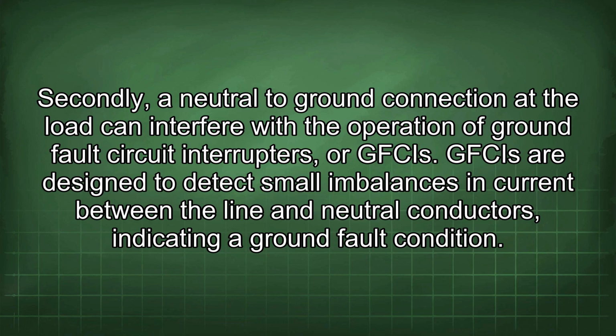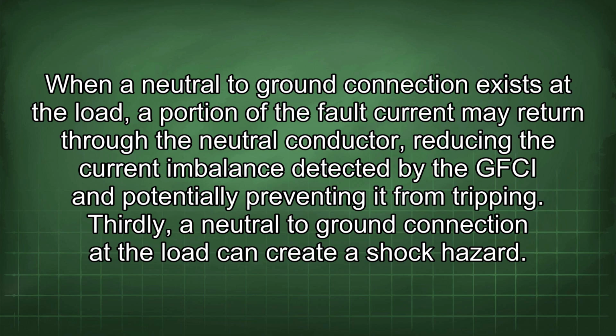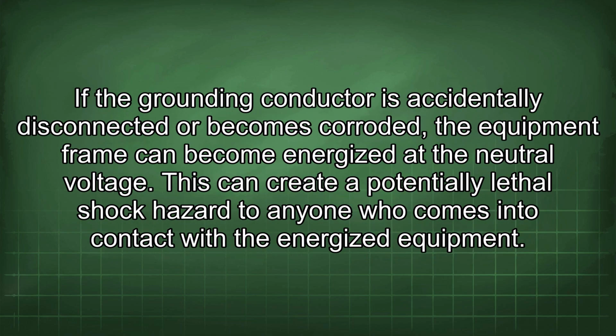Secondly, a neutral to ground connection at the load can interfere with the operation of ground fault circuit interrupters, or GFCIs. GFCIs are designed to detect small imbalances in current between the line and neutral conductors, indicating a ground fault condition. When a neutral to ground connection exists at the load, a portion of the fault current may return through the neutral conductor, reducing the current imbalance detected by the GFCI and potentially preventing it from tripping. Thirdly, a neutral to ground connection at the load can create a shock hazard. If the grounding conductor is accidentally disconnected or becomes corroded, the equipment frame can become energized at the neutral voltage. This can create a potentially lethal shock hazard to anyone who comes into contact with the energized equipment.